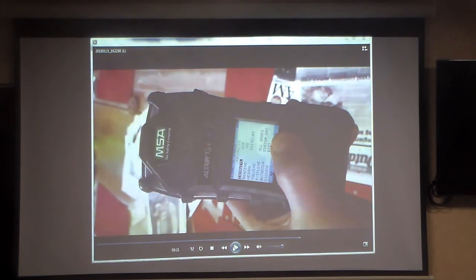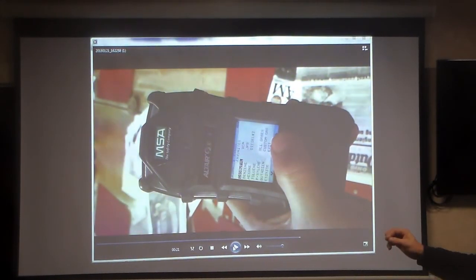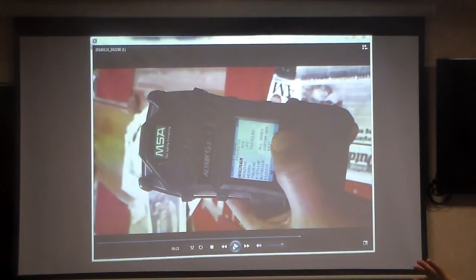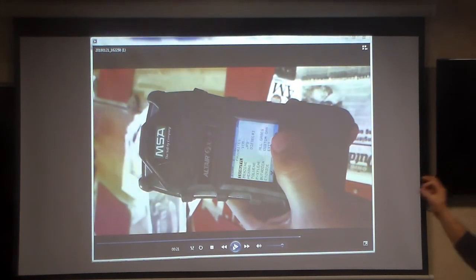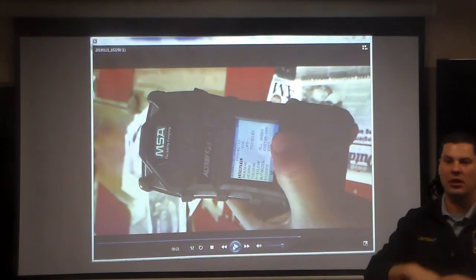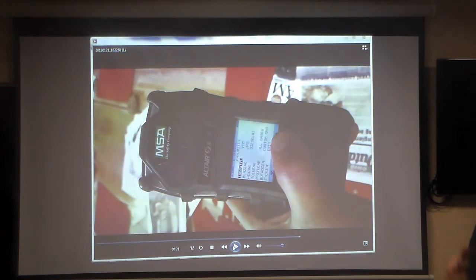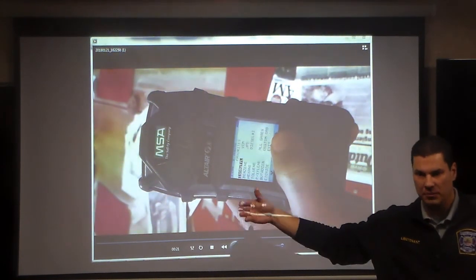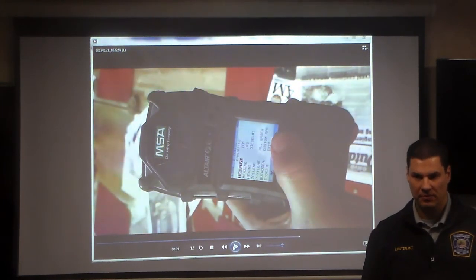Once you click that and select the gas, it just goes back to reading, and then it's only reading for that gas. Yeah, the PID is reading specifically for that gas. Just the PID part, everything else is still normal. You're still reading oxygen normal, LEL normal, all that stuff is going on normally. But the PID sensor is specifically reading for that gas, and it'll alarm at the certain numbers that are dangerous for that particular chemical.